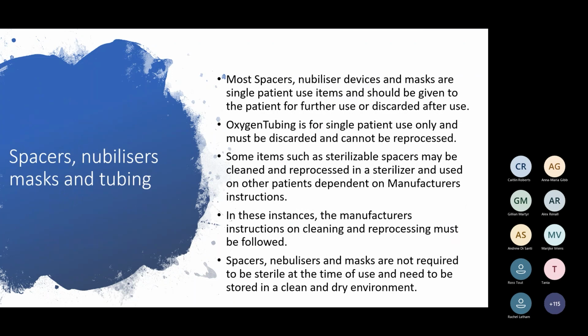It's a bit contentious about spacers and nebulizers and masks, but most spacers, nebulizer devices and masks are single patient use items and should be given to the patient for further use or discarded after use. Oxygen tubing is always single patient use only and must be discarded. Some items, such as sterilizable spacers, may be cleaned and reprocessed in a sterilizer and used on other patients, but that is dependent on the manufacturer's instructions, and you need to read the instructions for use when you get that spacer. If the manufacturer says it can't be reprocessed and used on another patient, then you can't do it. So always read your manufacturer's instructions.